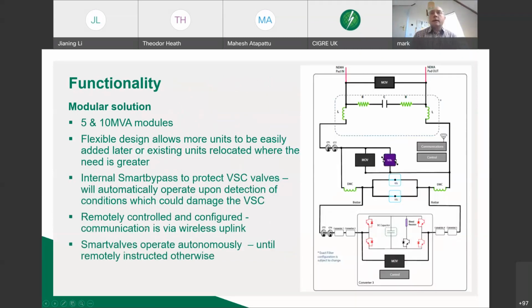So the technology is called Smart Valve, and it is a brand new kind of technology essentially on the world stage. What we have installed on the northern circuits is a modular solution based on, in our case, 10 MVA modules, which allow us to inject either a leading or a lagging impedance, and that can help control the power flows on those circuits, either pre or post fault. The bulk of the requirement is for a post fault condition to avoid overloading circuits, so we can optimize the capacity across an overall boundary.